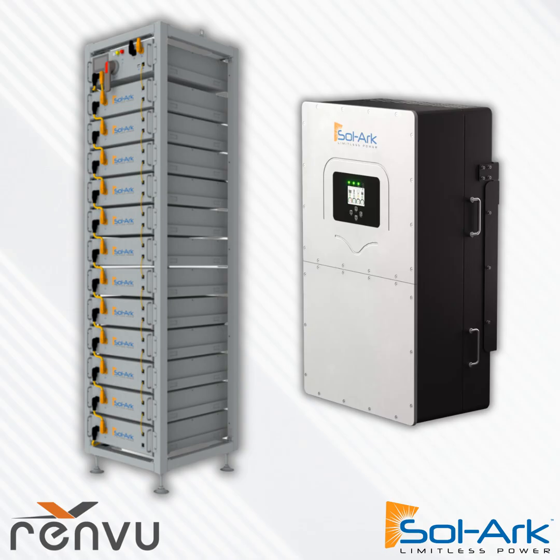So in a simple project, the meter lands on the inverter, everything lands on the inverter. You do the full grid pass-through to the main service panel, and that's a very simple whole-home backup project on a single inverter. What's nice about delivering an inverter large enough to be capable of whole-home backup — able to start a 4-ton air conditioning unit, that degree of magnitude — is that you can scale the batteries independently of the inverter.